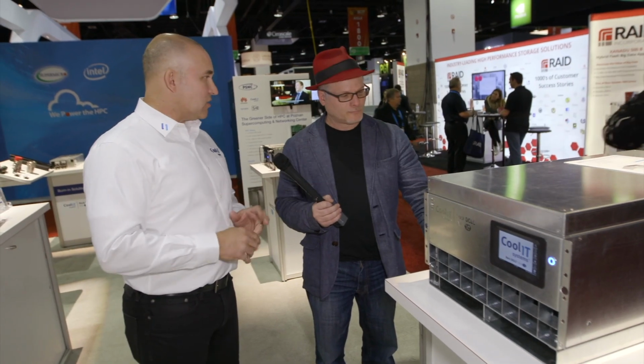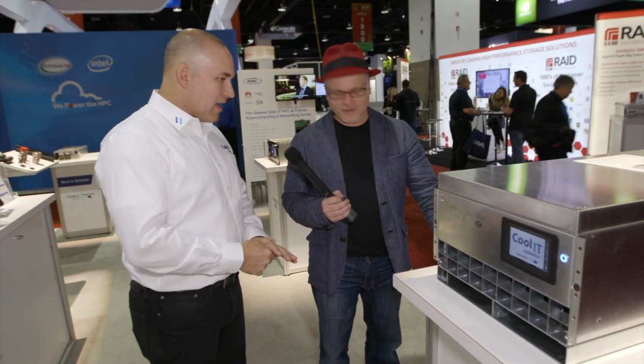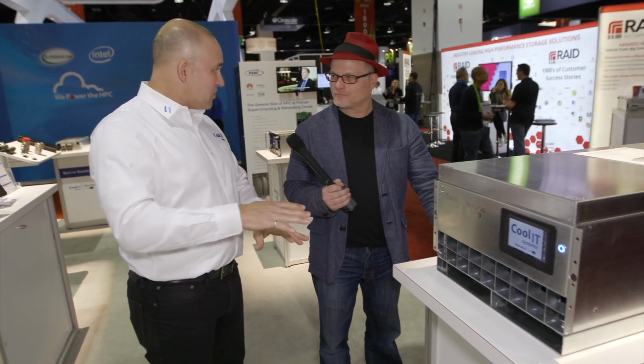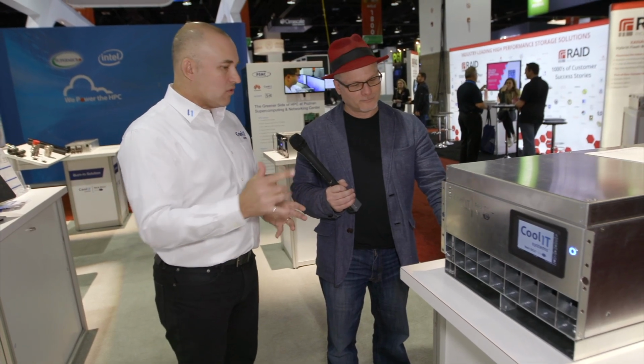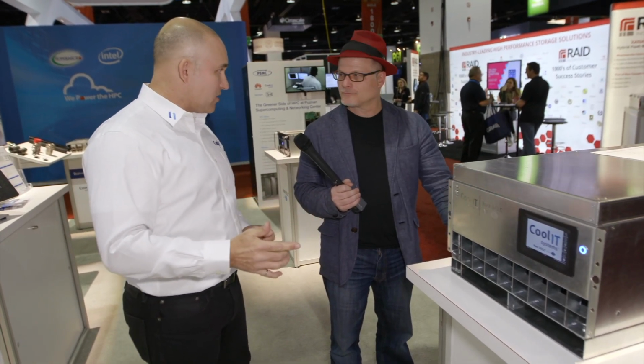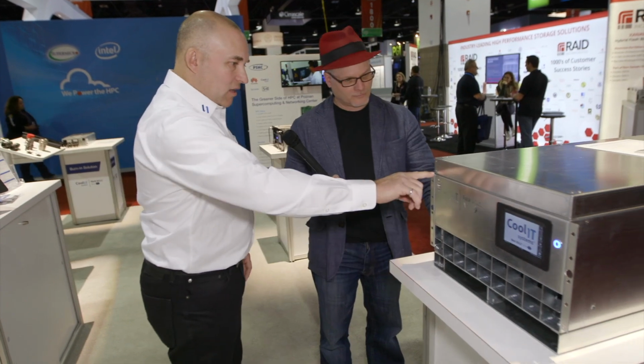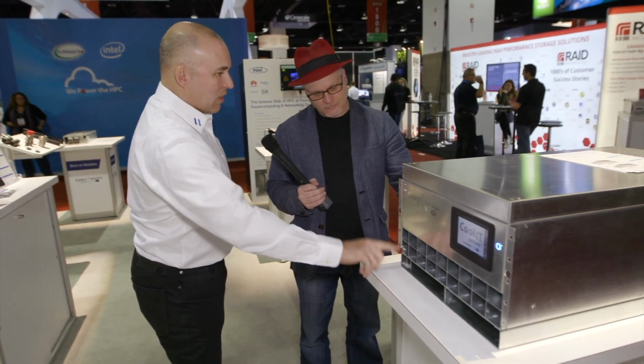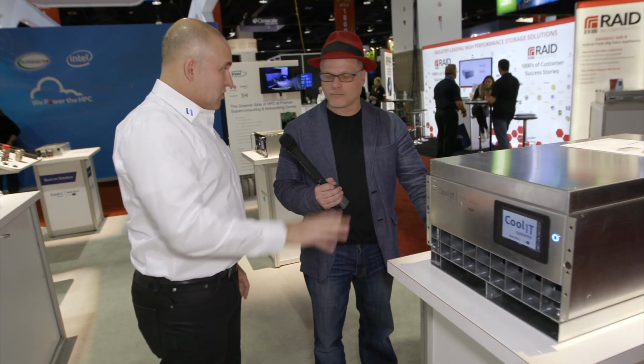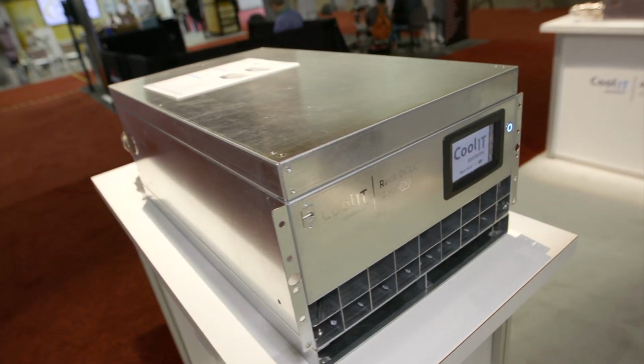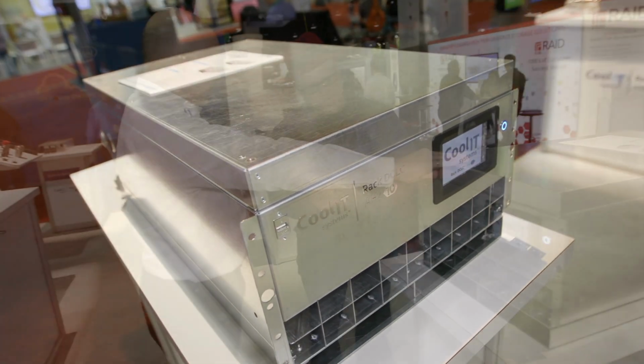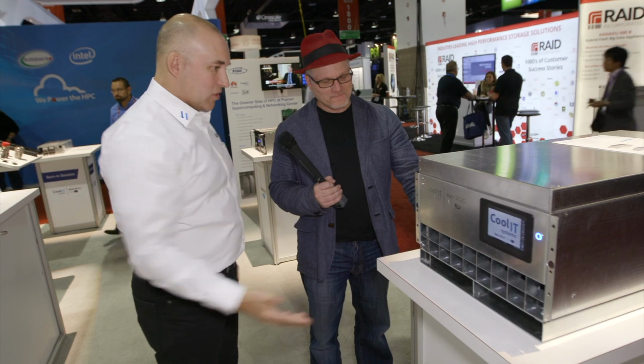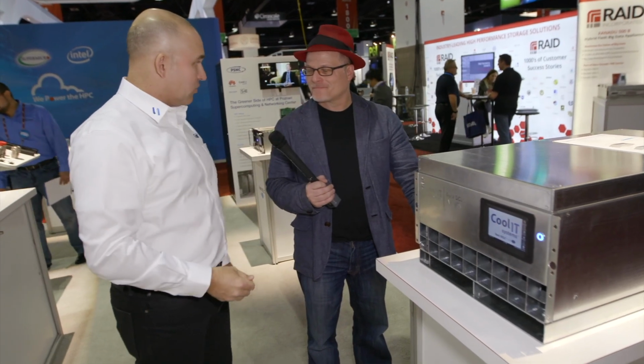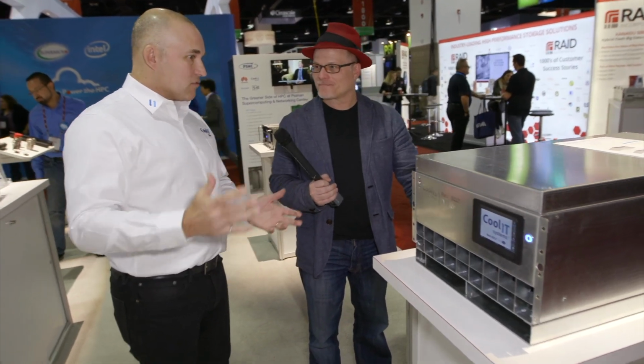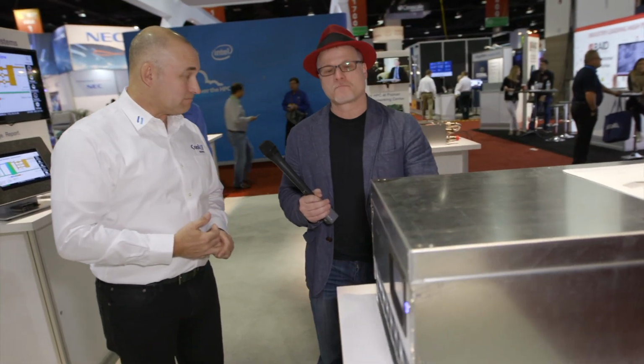So you put this into the rack. It actually mounts directly in the rack. It has a couple of options that are available. So if you would only need maybe 5 or 6 kilowatts of capacity, then it would be only 5U high. This is optioned up to allow more airflow. So it's basically got a hood scoop on the top and one on the bottom, which increases the amount of air that can go through the heat exchanger. And that gives us up to about 10 kilowatts.